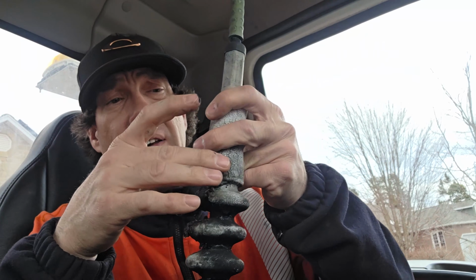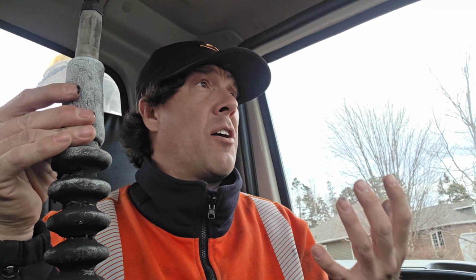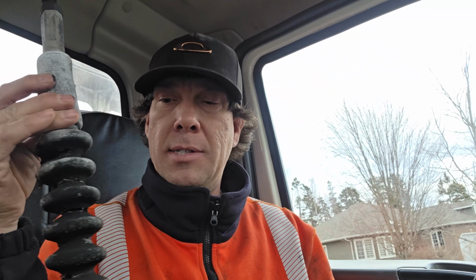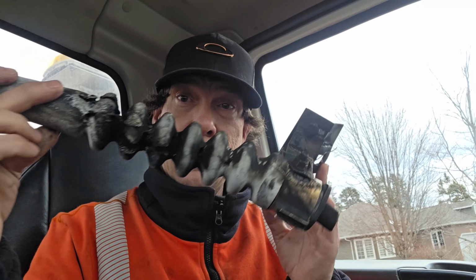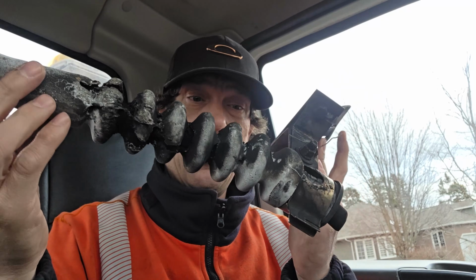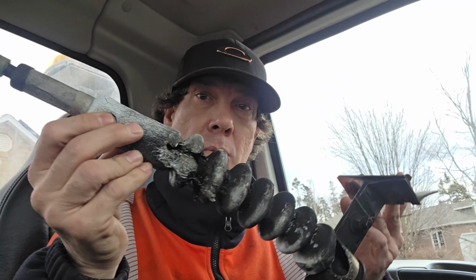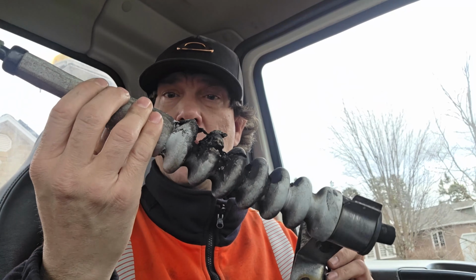The other cables were on fire. Had to dump the line to get the fire out. It was a bad scene. But let's go in the house and cut this guy open, see what it looks like inside, and see if we can figure out how this thing went to ground, where the fault was.